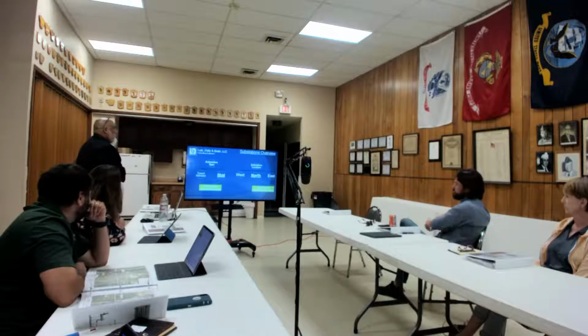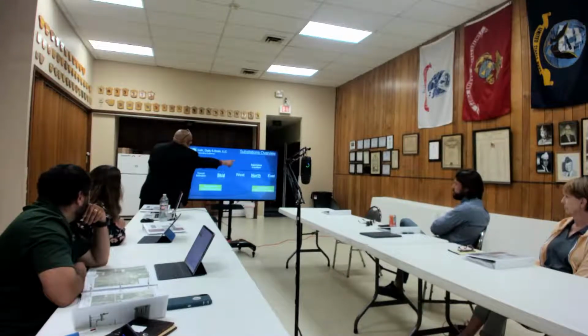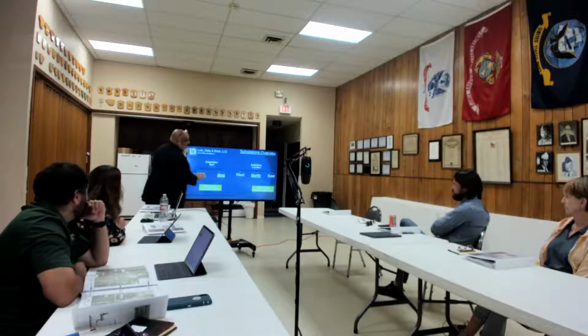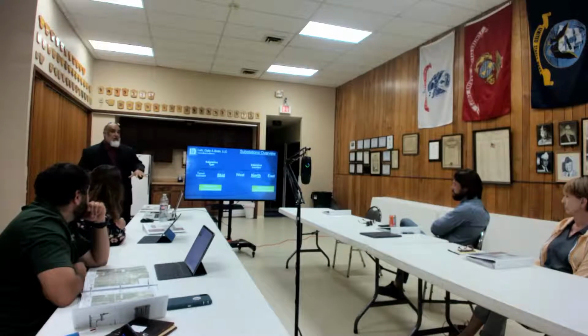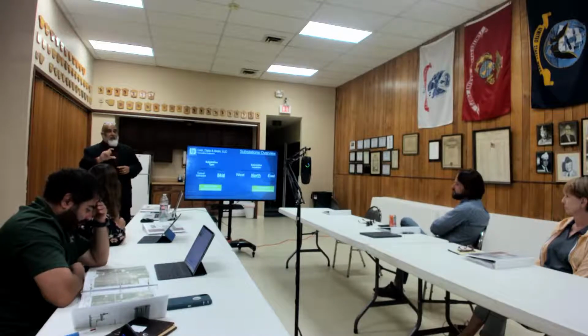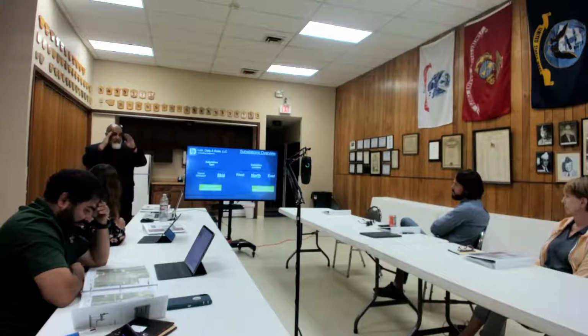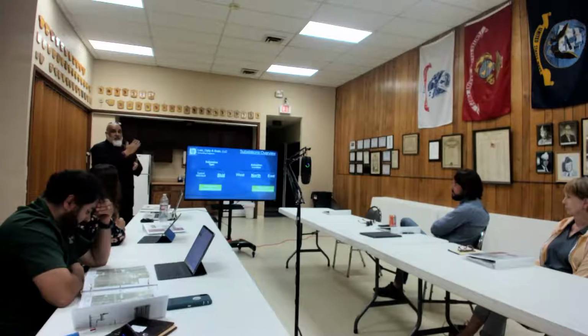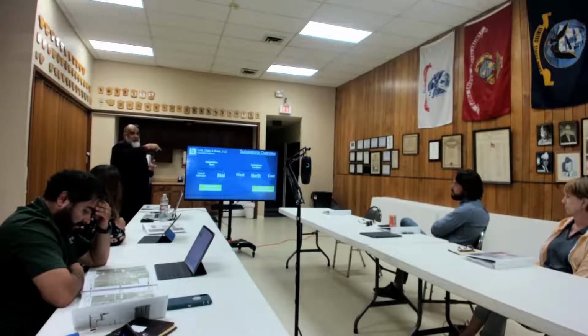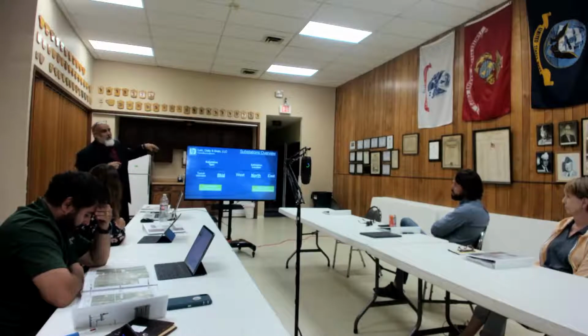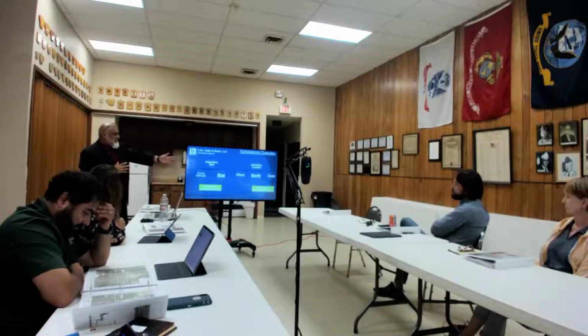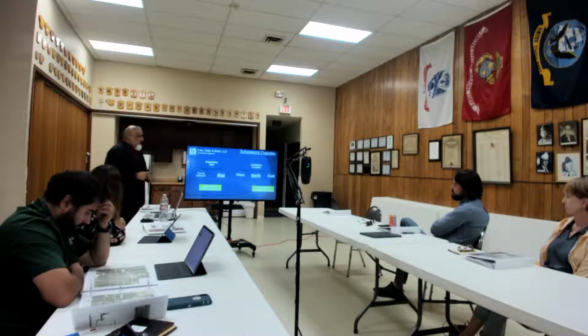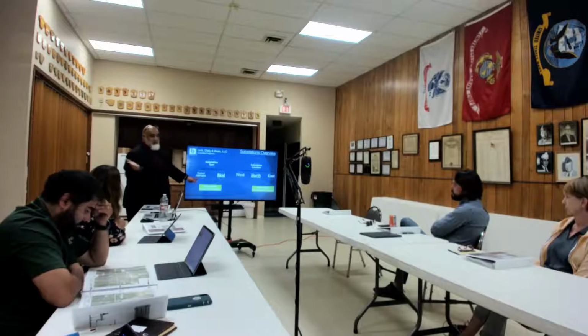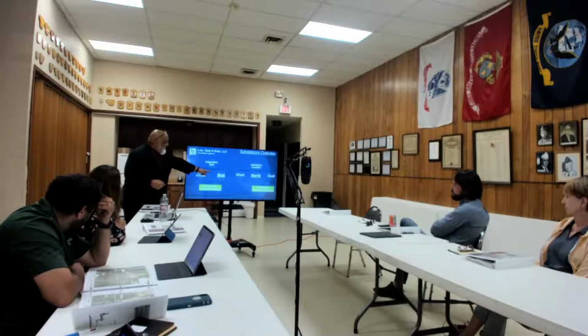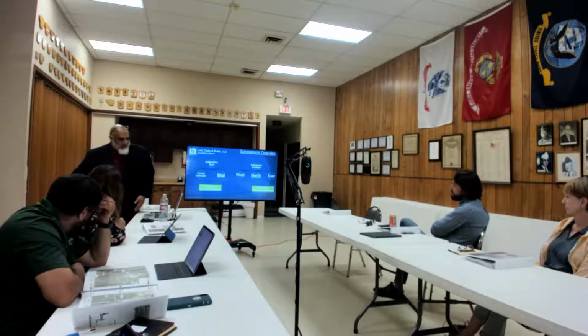So the punchline for the substations is that there are two choices to make: the location and the type. The location, I understand, is going to be really important to you guys on a more local level, so I've still framed my answer in a way that allows for a little room. When I say the north substation, that doesn't mean it has to be the north east corner of that intersection. It could be the southwest corner, or a block or two away. My opinion still stands that the north substation is the winner. As for substation type, you either have a typical standard substation like every utility in the U.S. deals with, or the skid-mounted type. My opinion is with the skid.